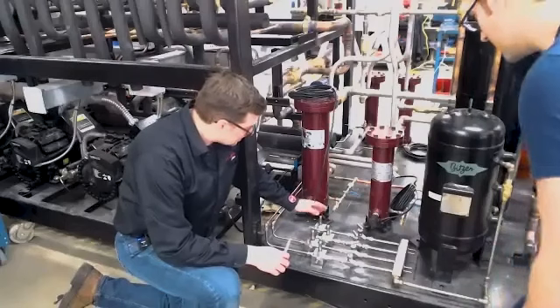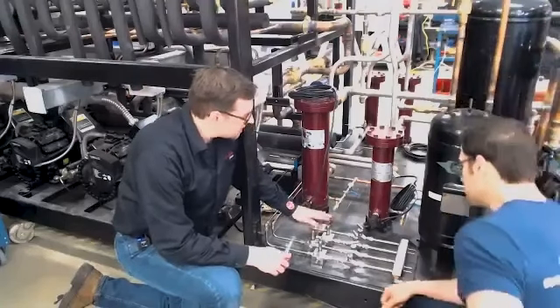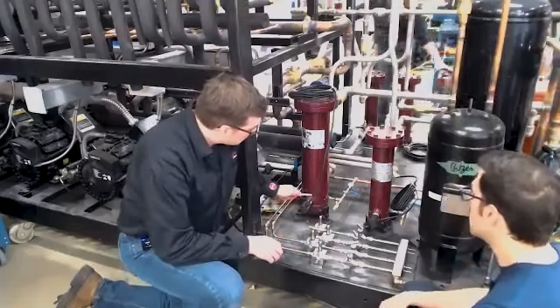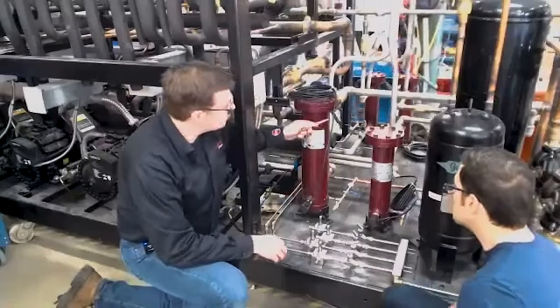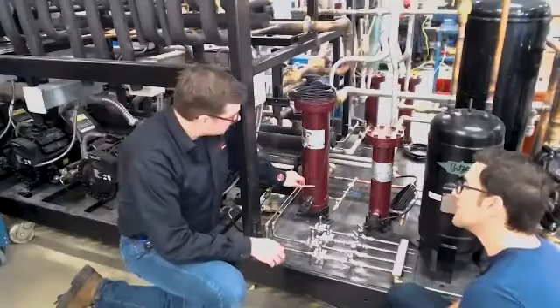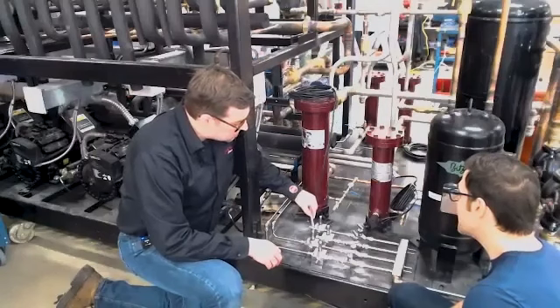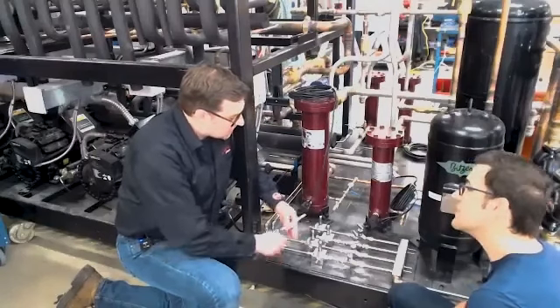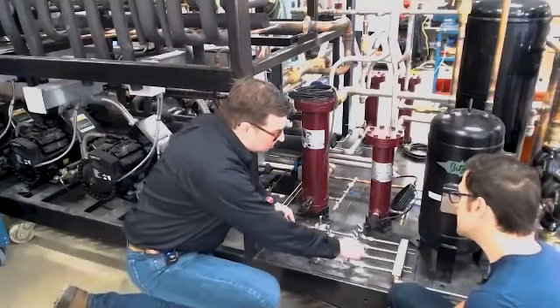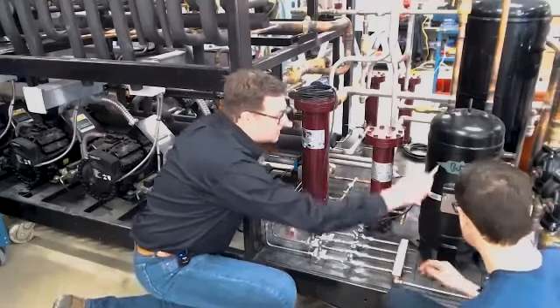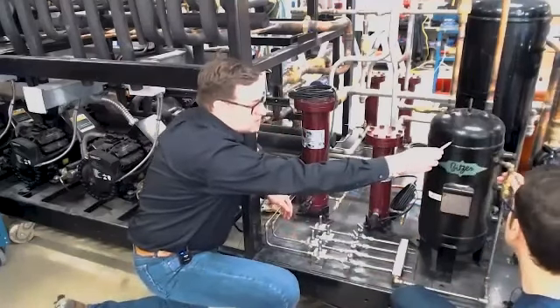It's interesting - so these are managed by your photo eye. Your photo eye sends a signal to your controller that we've got to drain oil. The block solenoid opens, and now we're going to bleed oil through into the manifold and into this oil receiver.